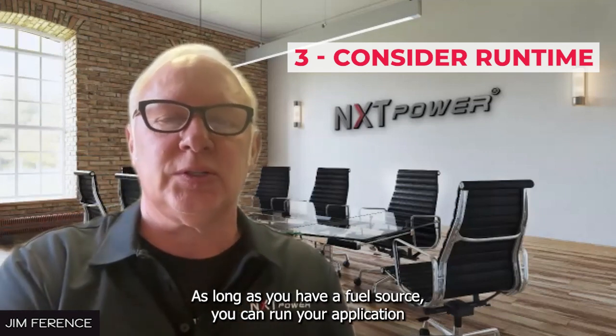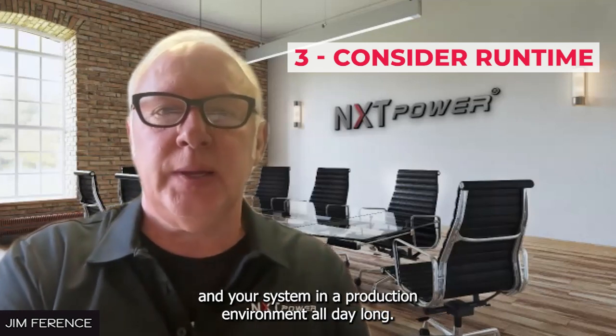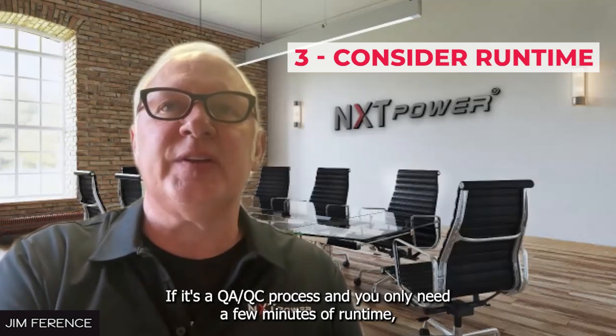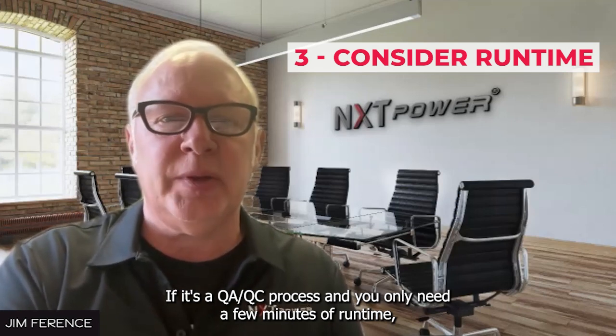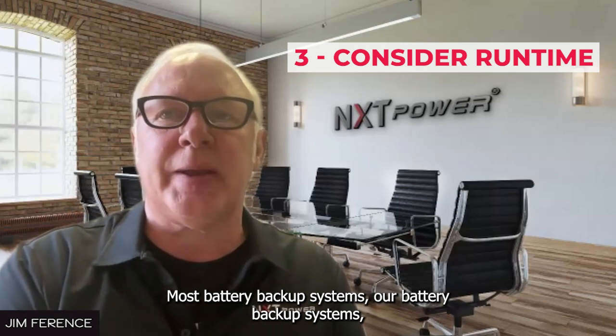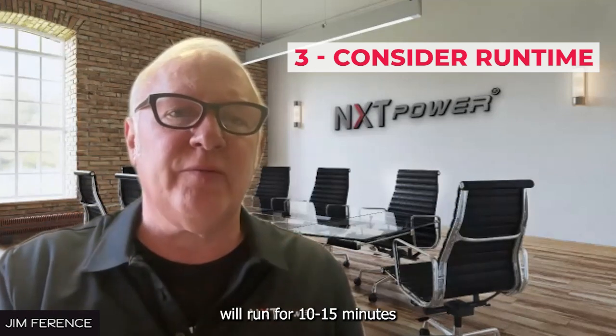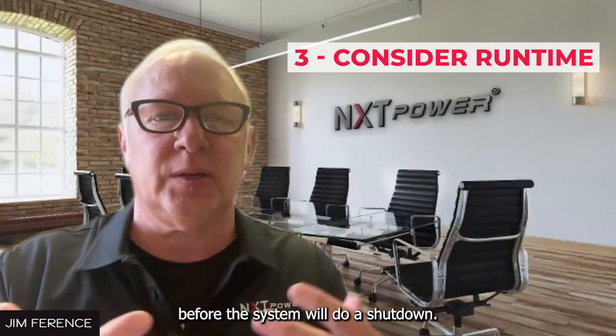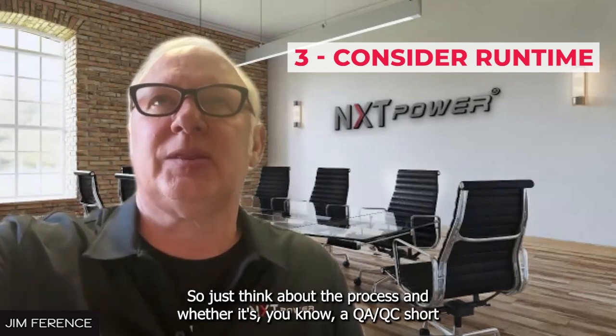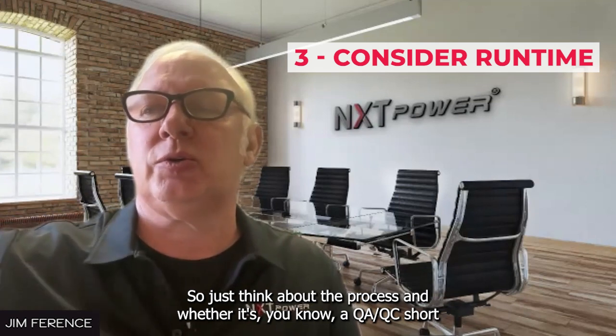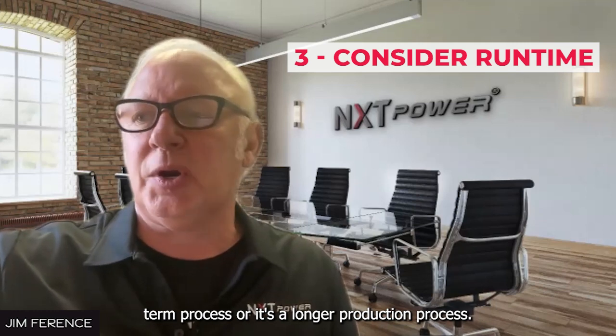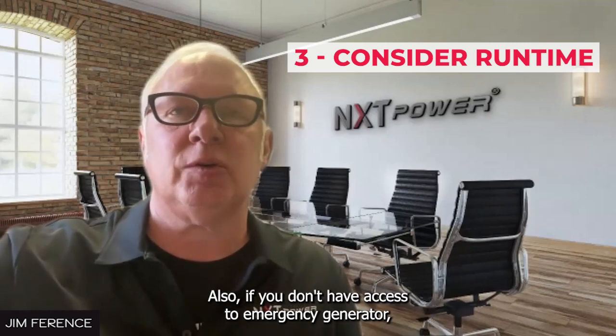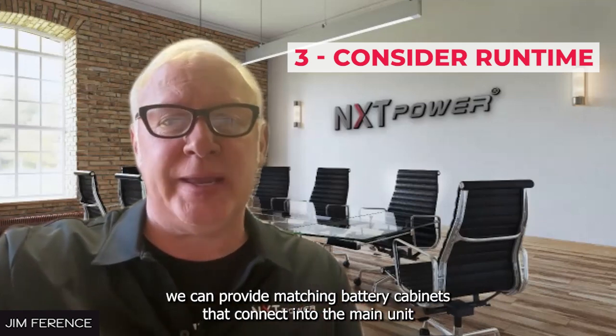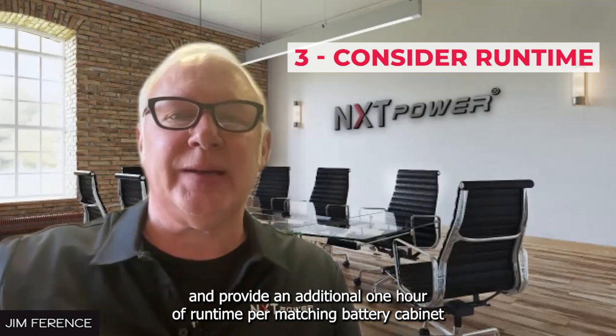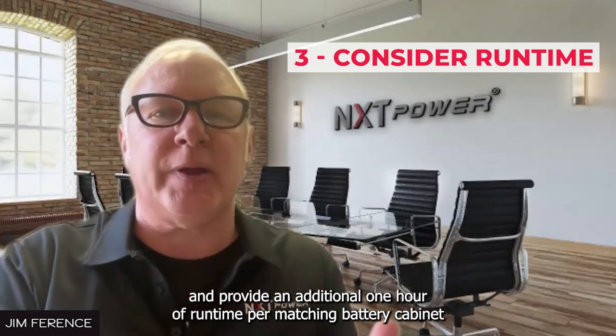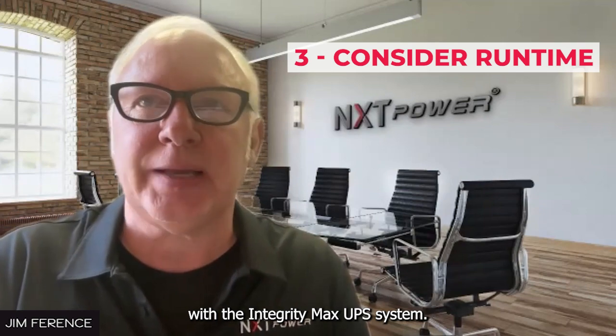As long as you have a fuel source, you can run your application and system in a production environment all day long. For a QA/QC process needing just a few minutes of runtime, we can do that too. Most battery backup systems will run 10 to 15 minutes before shutdown, so think about whether your process is a short-term QA/QC task or a longer production process. If you don't have access to an emergency generator, we can provide matching battery cabinets that connect into the main unit, providing an additional hour of runtime per cabinet with the Integrity Max UPS system.